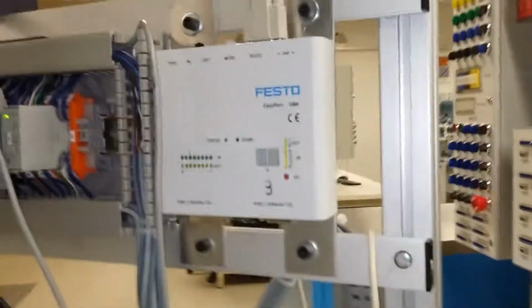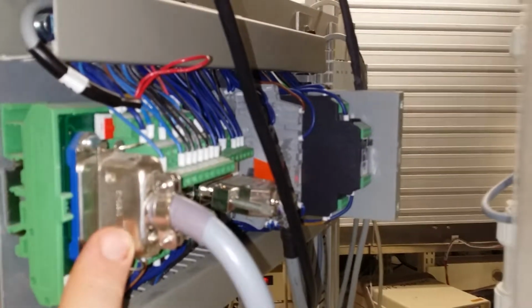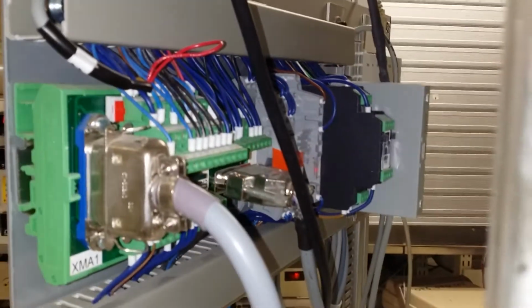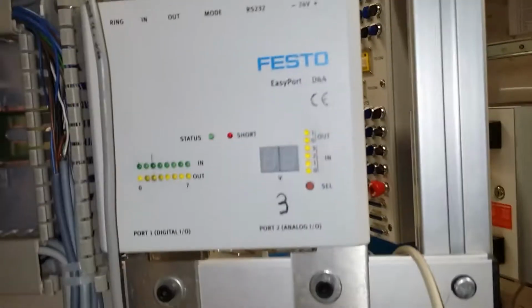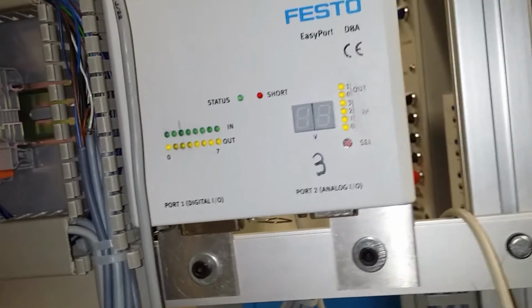It's going to be removed from this Festo I/O box, and the cable actually comes from, you can see these two connectors over here. One of them is for the analog input and the other's for the digital. I'll point them out. One is there and the second one's over there. So a lot of students will sometimes make the mistake of disconnecting that end and connecting to here, but that's what has to be disconnected.